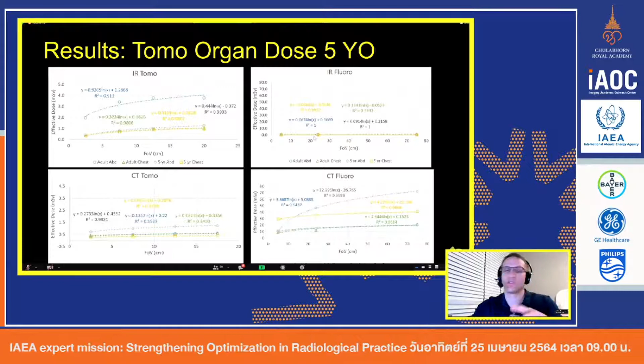Where they are different is the fluoro mode. So if you're on an interventional C-arm and you just step on the pedal and you're doing normal fluoroscopy, here you can see I fixed my ordinate axis, so they're the same. You can see that the fluoro dose is just nothing. It's right there on the 0 mark. It's actually higher than 0, don't get me wrong, but it's less than 10.